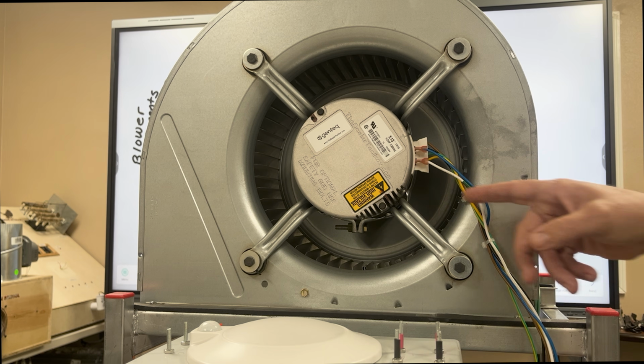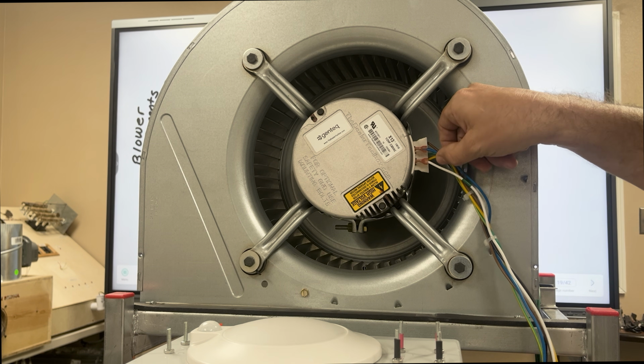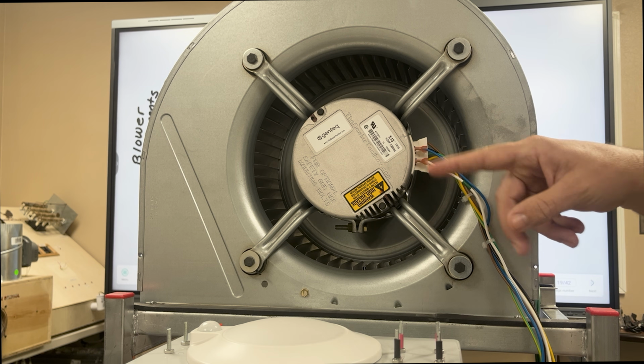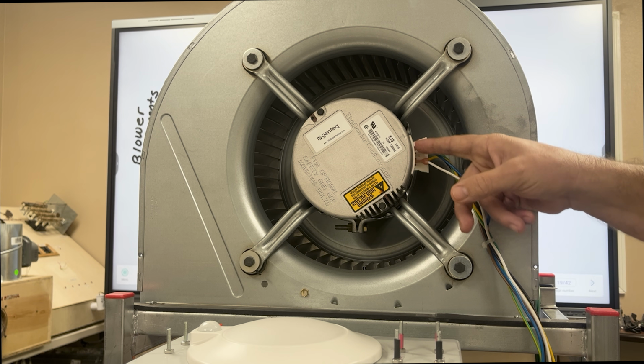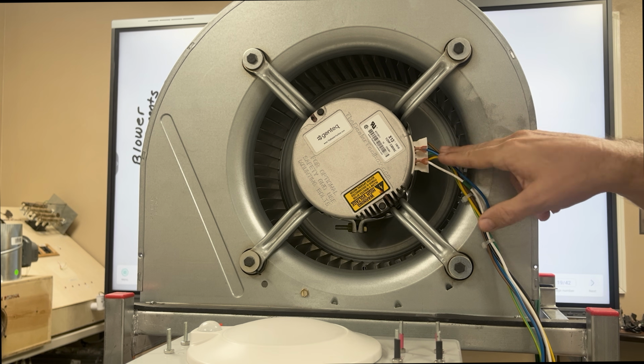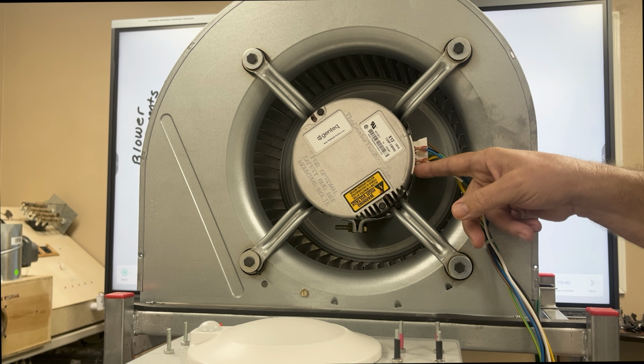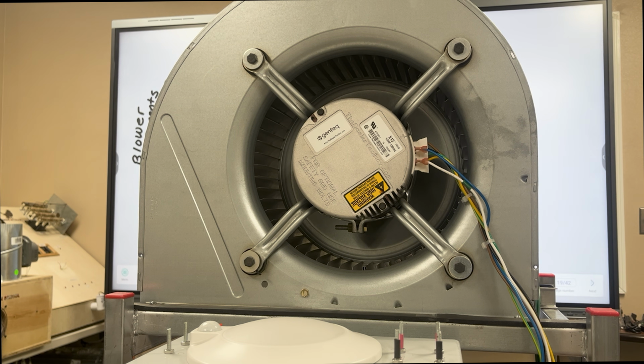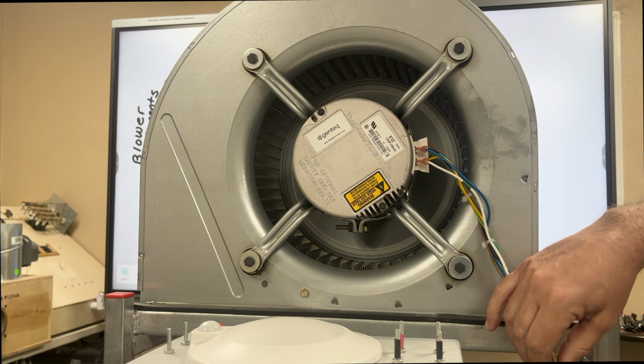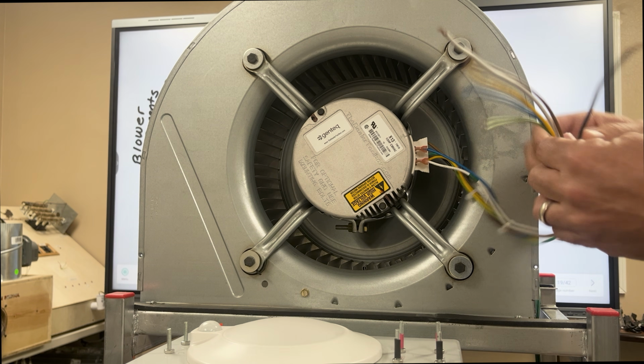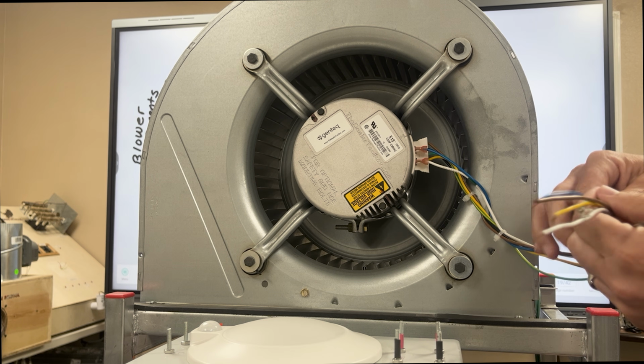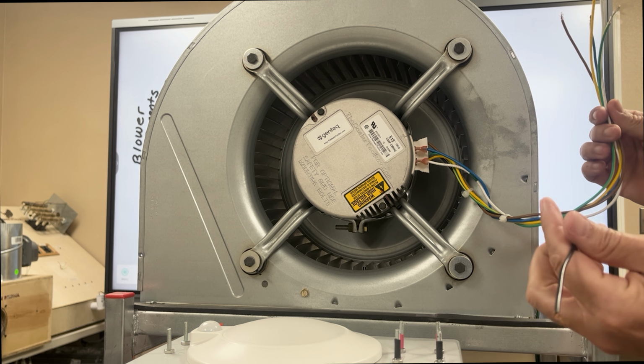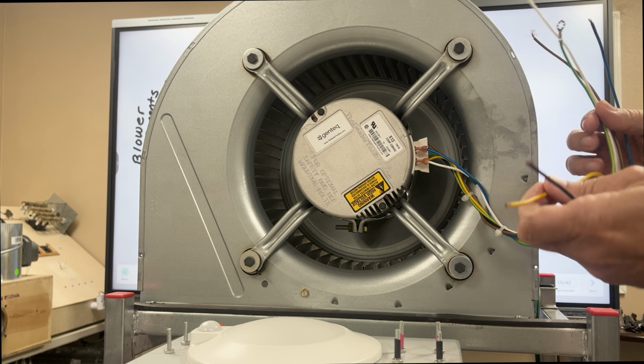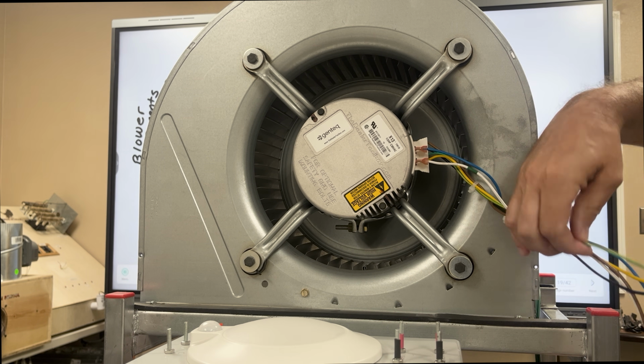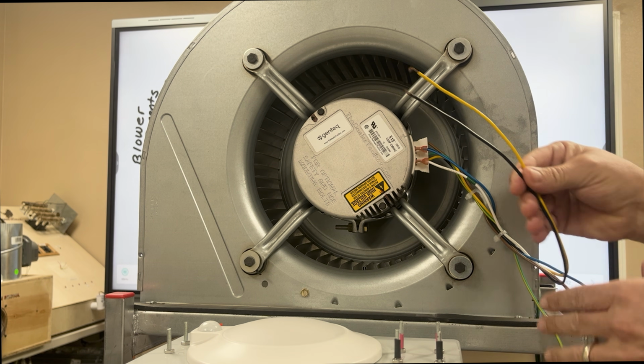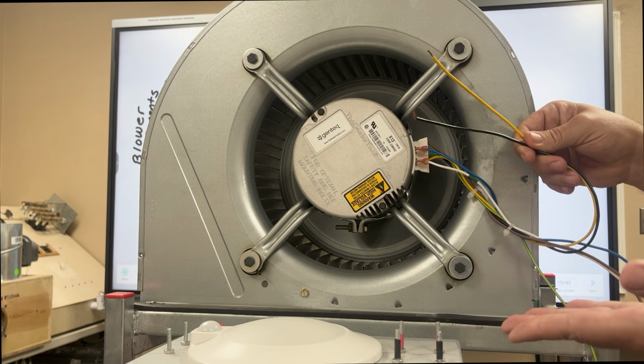The speed taps on here are where this blue and white wire are. I'm not going to change the speed taps with these. I'm actually going to have another demonstration where I show you with alligator clips, very carefully, how we can get in here without all these plugs and see the terminals a little better. So what we're going to do is take our high voltage and separate those. We know we have black, we have yellow, and there's obviously the green with the yellow stripe, that's our ground wire. And we're going to take these two and put these on our line voltage.